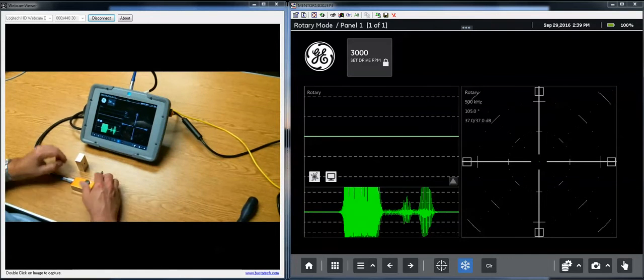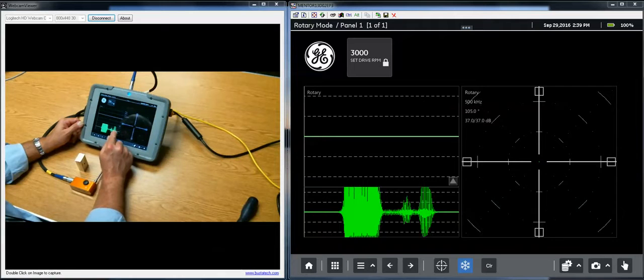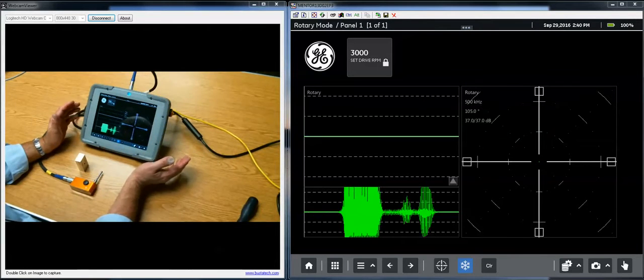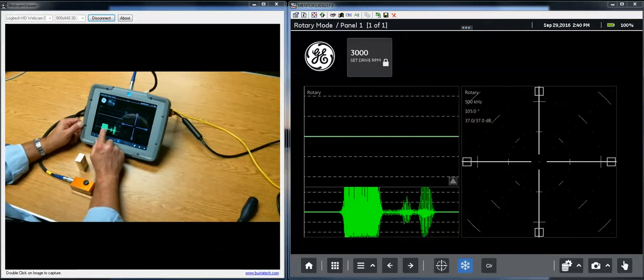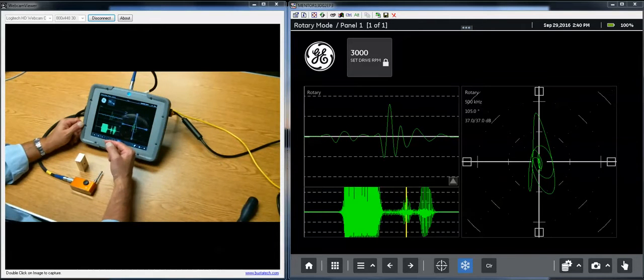Now what I see in the overview is every rotation for the last couple of seconds. So my gestures work a little bit differently in rotary mode than they did in surface mode. Now if I put my finger down and I place a cursor, the cursor will just follow the movement of my finger. And the cursor will always stay exactly one rotation wide, and whatever I select with the cursor is one rotation of the probe. So I see the indication on the Lissajous, and I see the indication on the time base that goes with the rotation of the probe that's underneath the cursor.